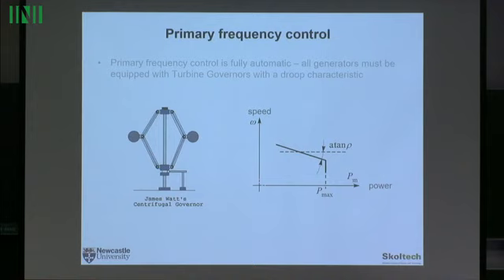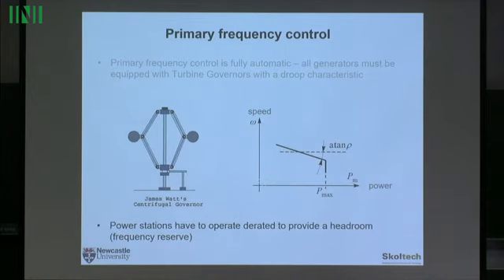Those controllers have a so-called droop characteristic. If you look at speed or frequency versus power, as frequency drops, the amount of power increases up to the maximum. That means in order for the whole thing to work, power stations must not operate at maximum output, but must have some headroom in order to release extra power if needed when the frequency drops - and they have to do it.